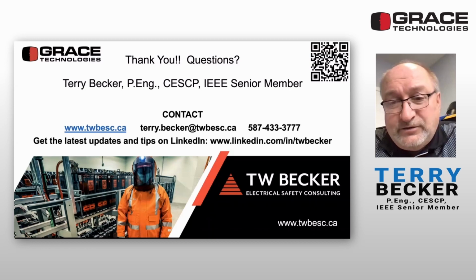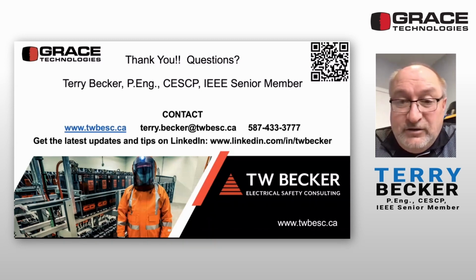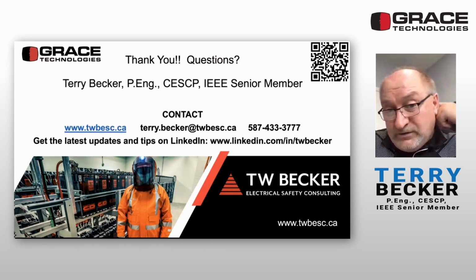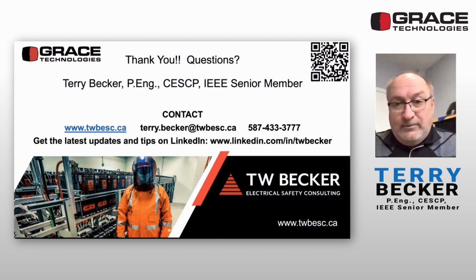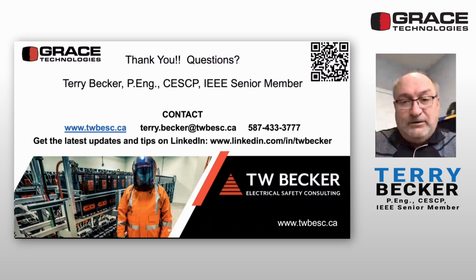Why are there new boundaries for capacitors? Because of the research done by the DOE. Mark Scott is the name of the engineer at one of the labs down there. He said, I've come up with this information. He presented it publicly, with white papers. He defined these two new boundary distances, and then it was accepted and included in 70E with specific formulas for these distances.